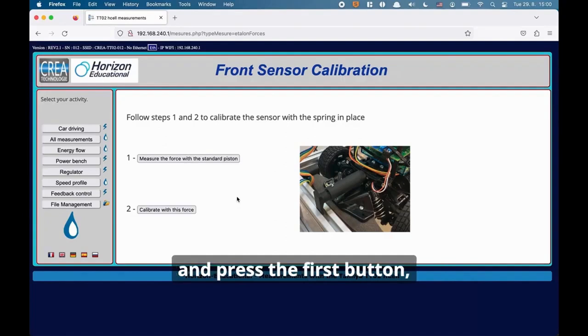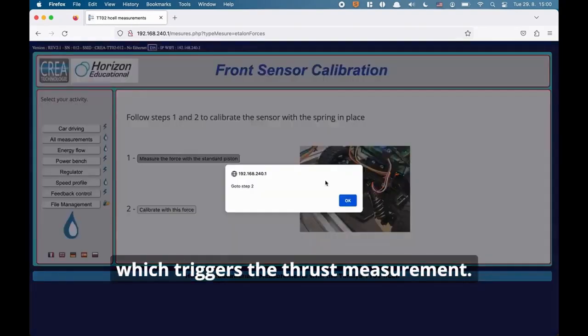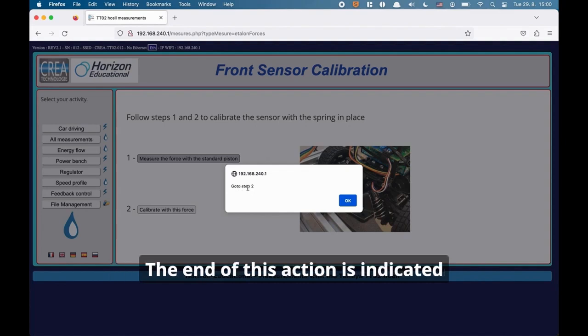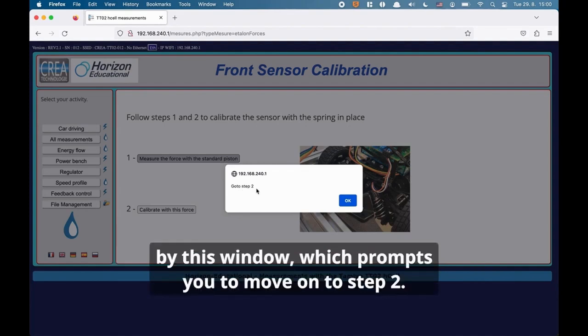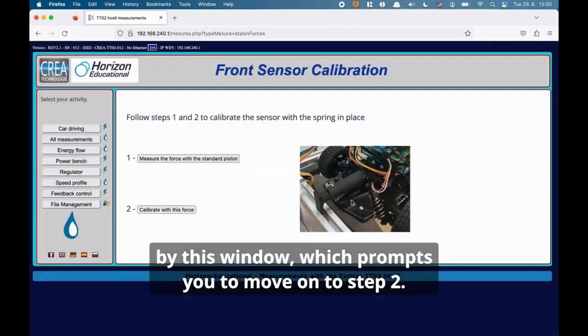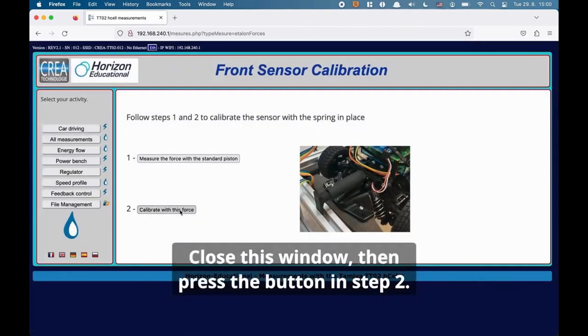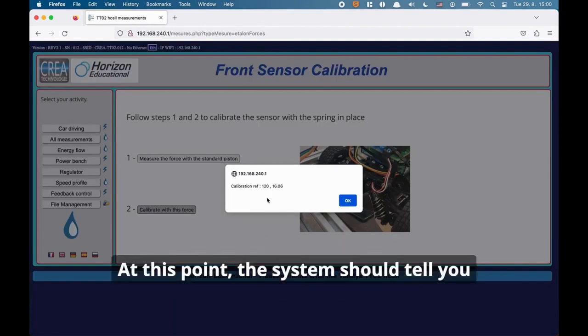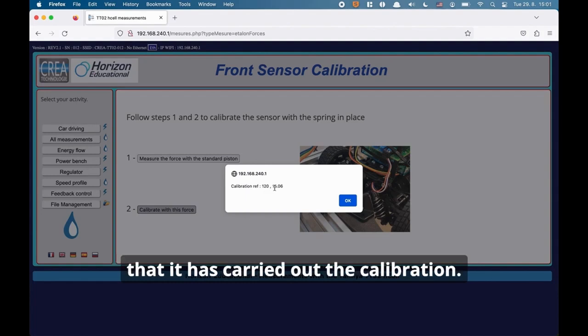You press the first button, the button for step one, which will trigger the thrust measurement. The end of this measurement is indicated by a window prompting you to move to step two. You exit this window, then press the button for step two. At that moment the system should indicate that it has performed the calibration.